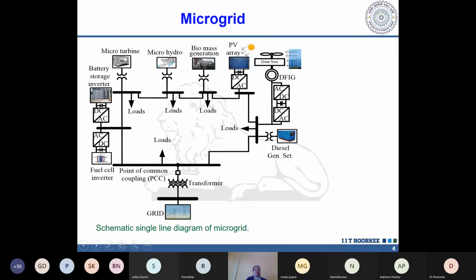Here we have a micro turbine, and this is a connecting transformer. This connecting transformer is present because if the voltage level is not equal to that of the ring main or mesh network of the AC low voltage distribution network, we have to step up the voltage. Mostly these are step-up transformers, known as connecting transformers.